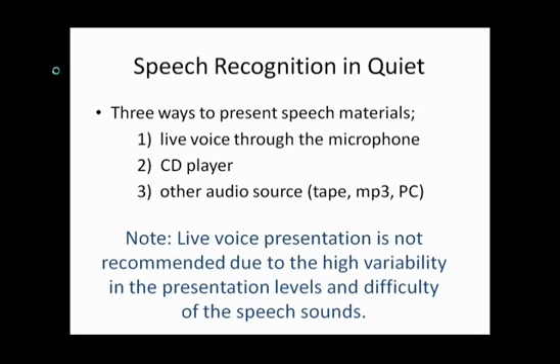There are three ways to present speech materials: through monitored live voice using a microphone, through a CD player or another audio source such as an MP3 player or PC, or via tape in older days. Live voice presentation is not recommended due to high variability in presentation levels and difficulty of the speech sounds. Monitored live voice, though unfortunately widely used today, can adversely affect test results.